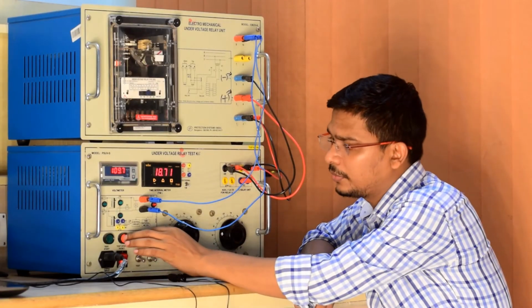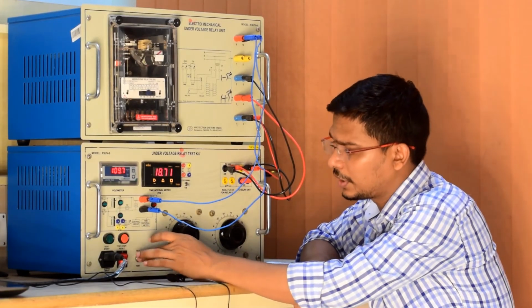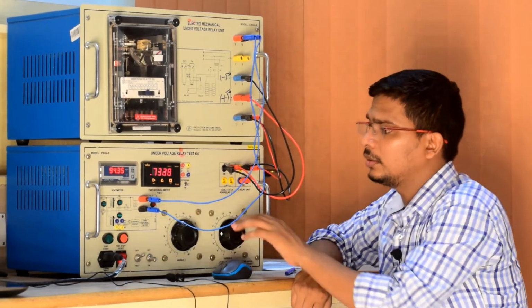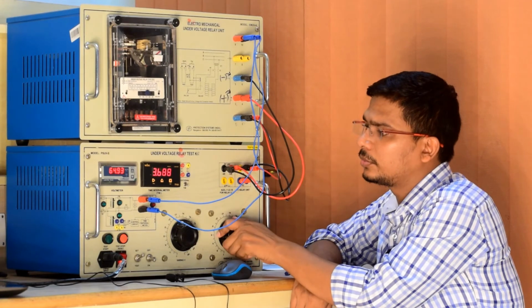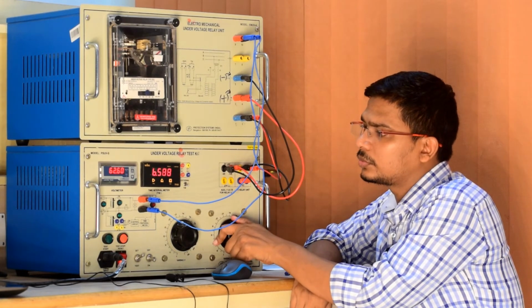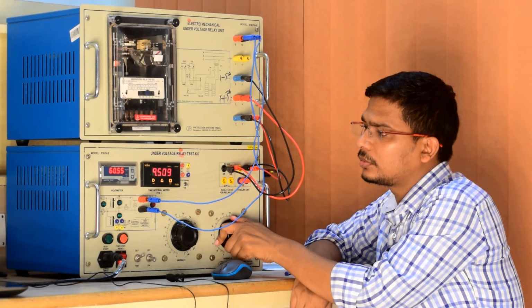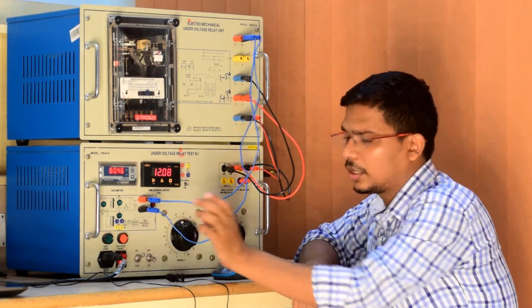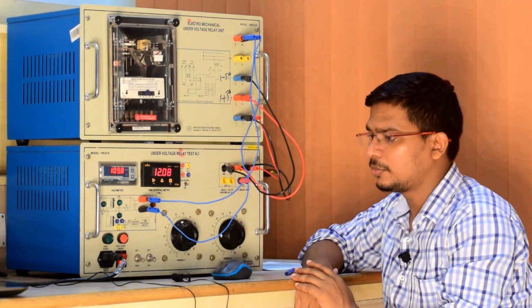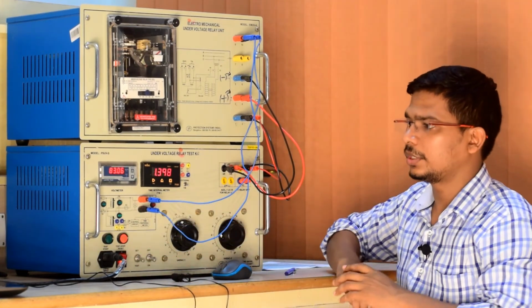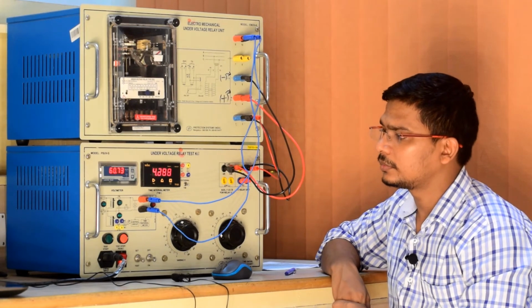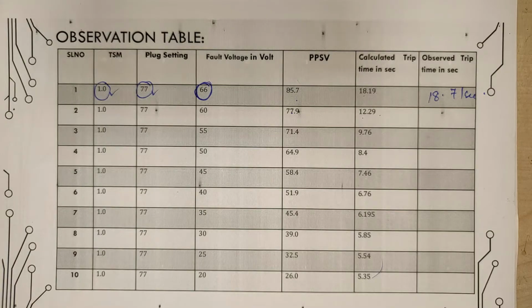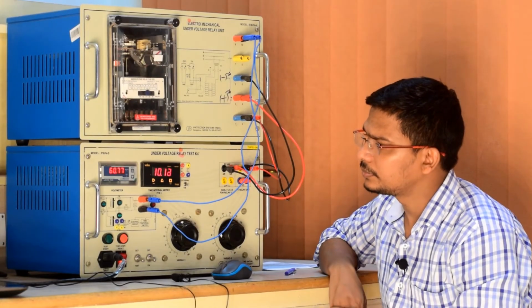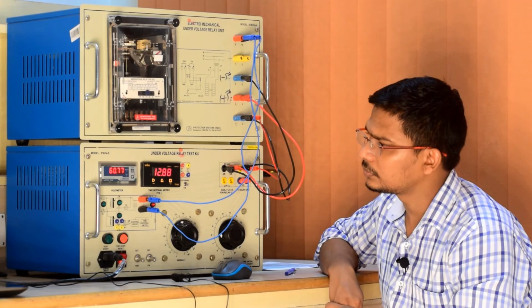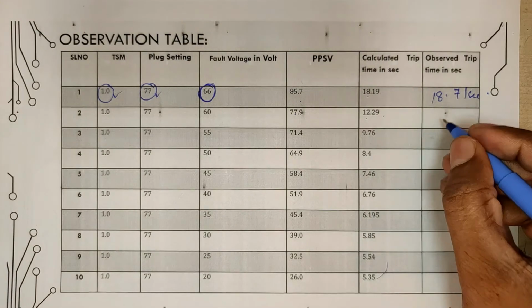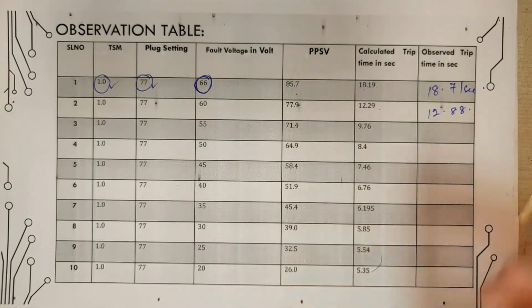Next is 60 volt. We have already turned off. So we have to put to set mode, turn on, and reduce to 60 volt. Okay, 60 volt we have applied. We have to turn off the circuit breaker, change to test mode, then apply the 60 volt directly. How much are we expecting? 12.3. 12.8. So what we expected is coming, till now 12.88.